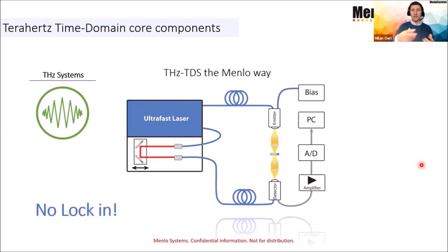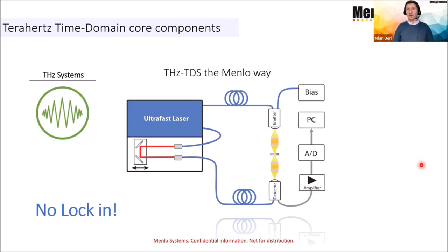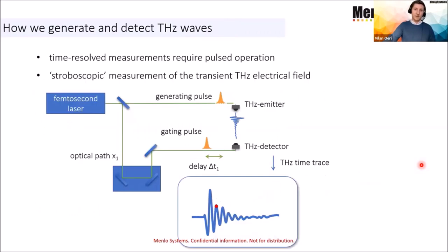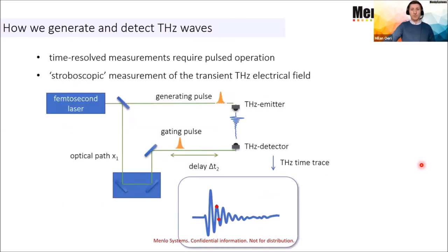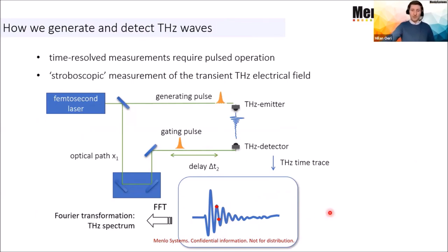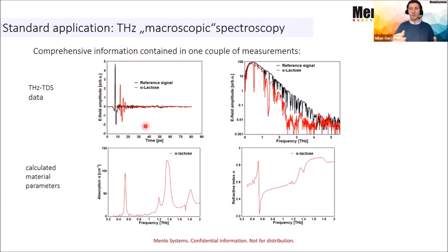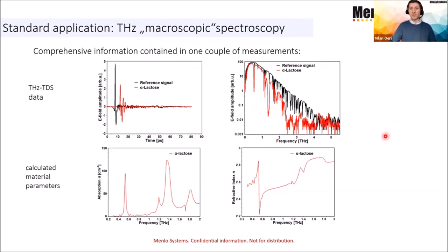I'd like to remind you that all this process works without using any lock-in amplifier, simply because the acquisition is such fast and the PCAs deliver a high signal-to-noise ratio. By applying a delay line, which can be a motorized stage moving back and forth, we can sample the Terahertz time trace at different timestamps and calculate the Fourier transform to achieve the spectroscopic information of the material applied. What you earn from this measurement is, per definition, a time-resolved signal which can be applied to thickness measurements, but also gives a spectroscopic footprint for different materials.